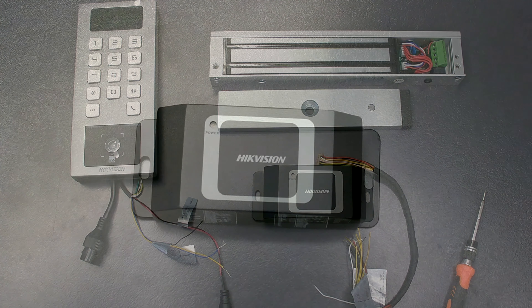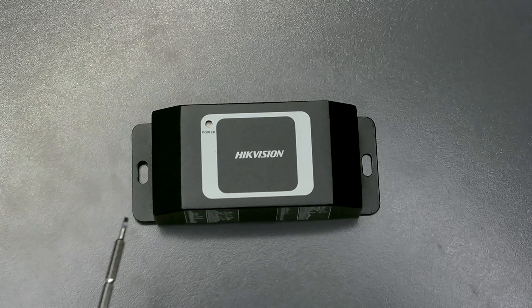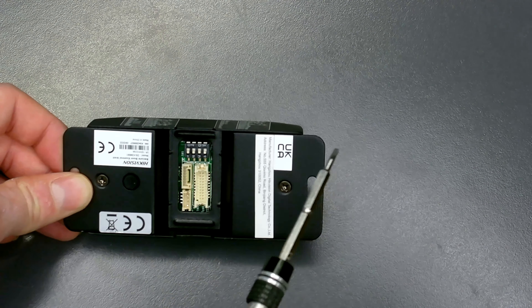Let's take a look at the secure module itself. This is our secure module which you would install on the secure side of the building. The only light you get on these new 061s is a power light — the predecessor 060s had a range of different status lights. Flipping it over, we've got our terminal port for the cable going to the lock and our RS485, and a set of dip switches. We use dip switches 1 to 3 for our RS485 to give it the right address. Dip switch 4 is for the Wiegand protocol — down for Wiegand in, up for Wiegand out. We're not using Wiegand, so we just use dip switches 1 to 3. We're going to use dip switch 1 because it's going back to one device, so the address for this device will be address number 1.